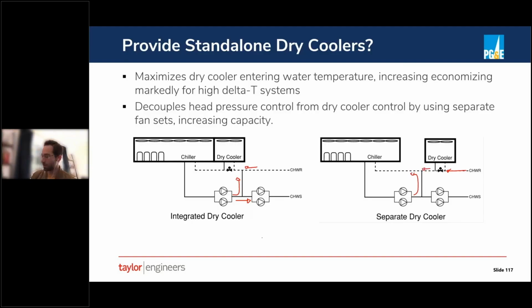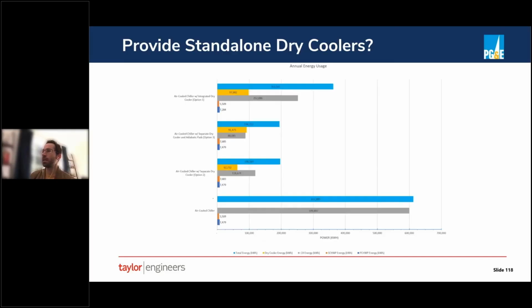So it's an important consideration, and one where we did an analysis for a small system for an owner a couple of years ago. And our annualized energy calc suggested that the system with an integrated dry cooler, so the option from the manufacturer, had roughly on the order of, believe this or not, 2 times the annual energy use of the option with a separate dry cooler. And the answer here is going to vary significantly based on your system.